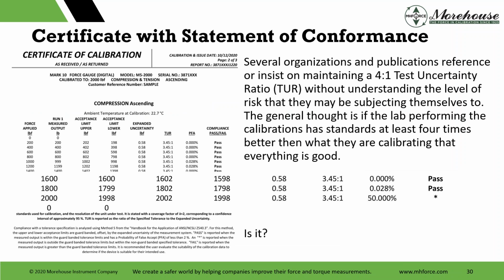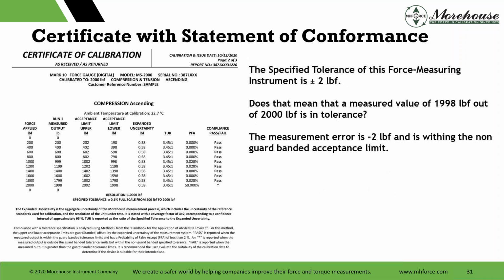What I need to say is several organizations and publications reference or insist on maintaining a 4-to-1 test uncertainty ratio without understanding the level of risk they may be subjecting themselves to. I know this is controversial saying this to everyone. I know people reading this might say, wow, we will have the uncertainty if we maintain 4-to-1. Not always true. A lot of it is dependent on the location of the measurement. And the general thought is that the lab performing the calibration has standards at least 4 times better than what they've got, that everything is good. There are a lot of cases where it's not.